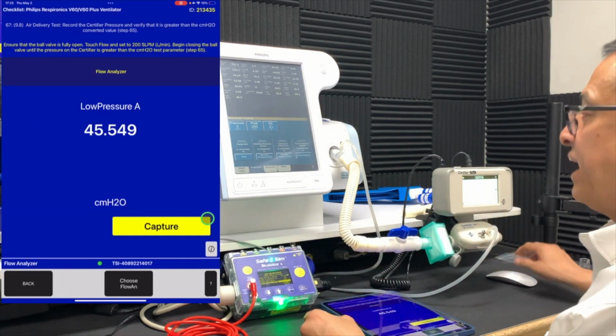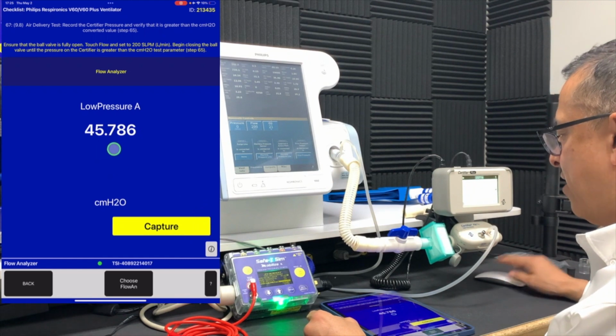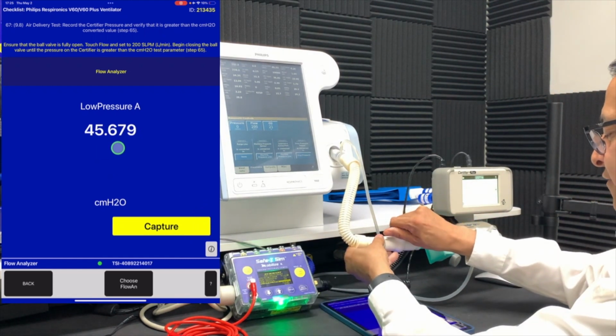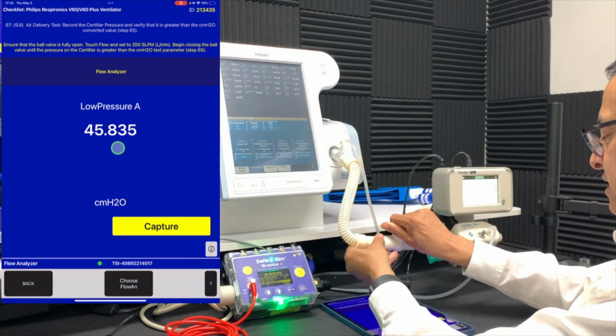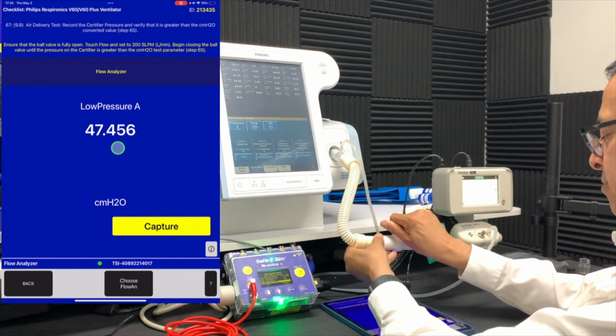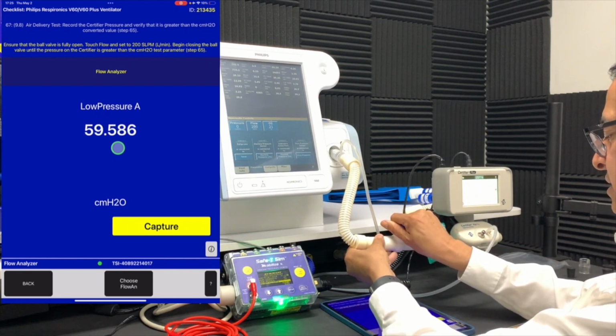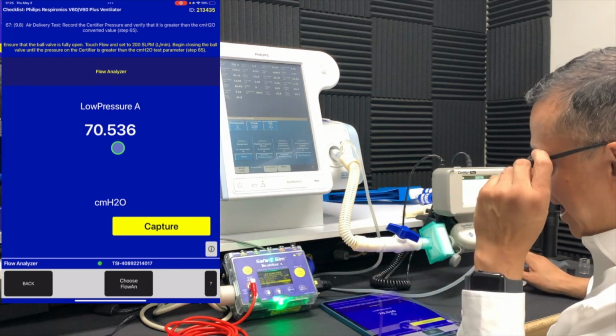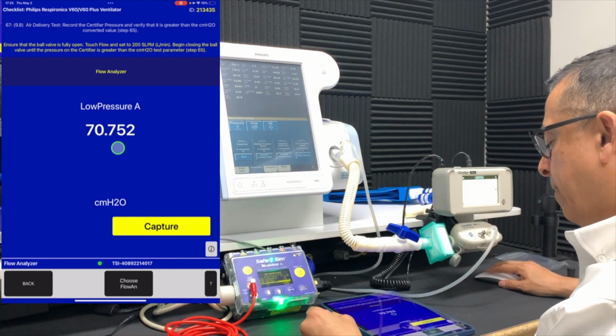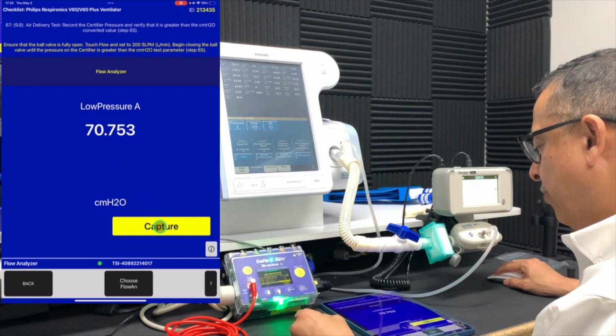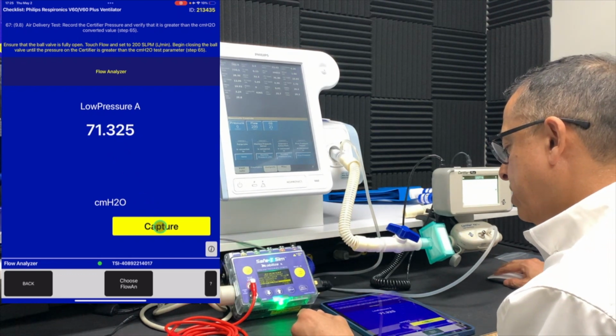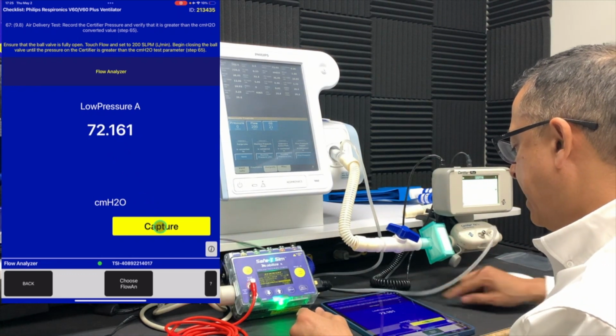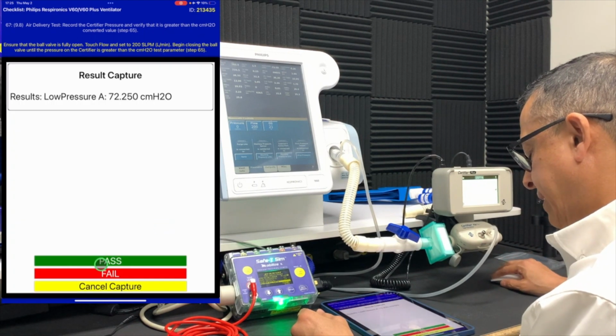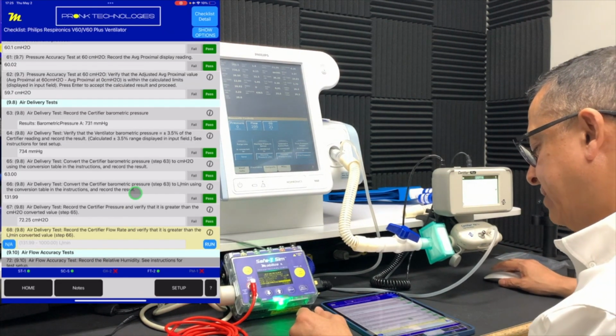And we can see we're getting a value of 45 on our certifier. I'm going to start to close this valve. We're getting above that. You can see I got it to around 70.7 or so, higher than what I needed it to be. So I went ahead and captured that number into my report, and we completed that test.